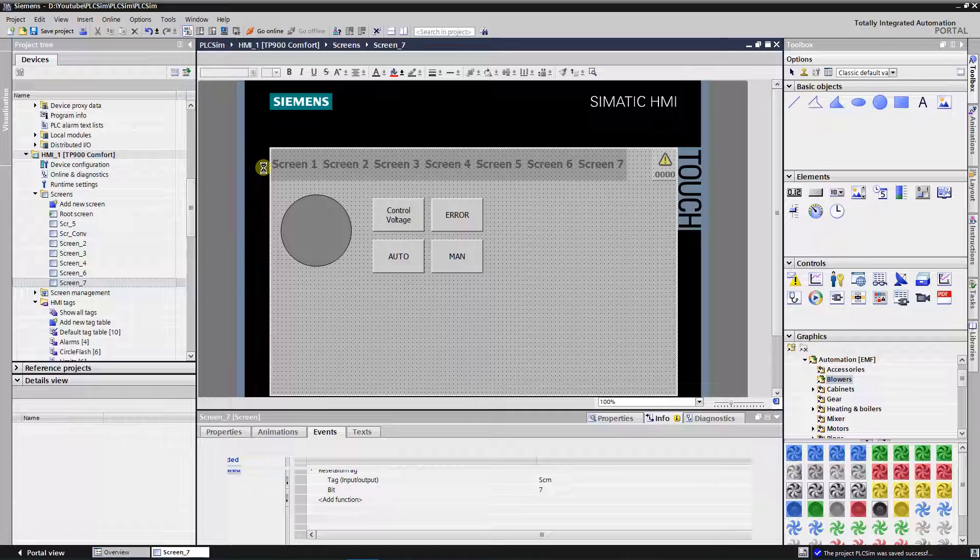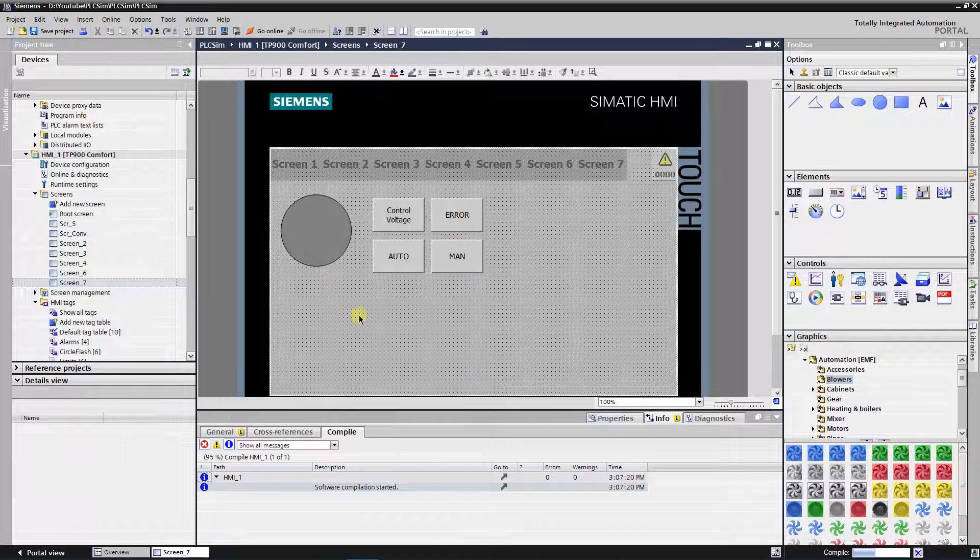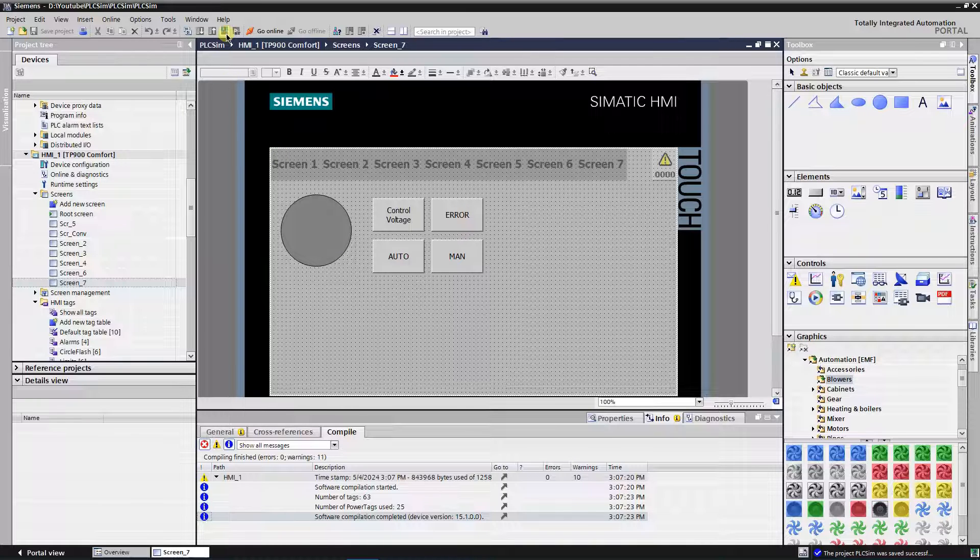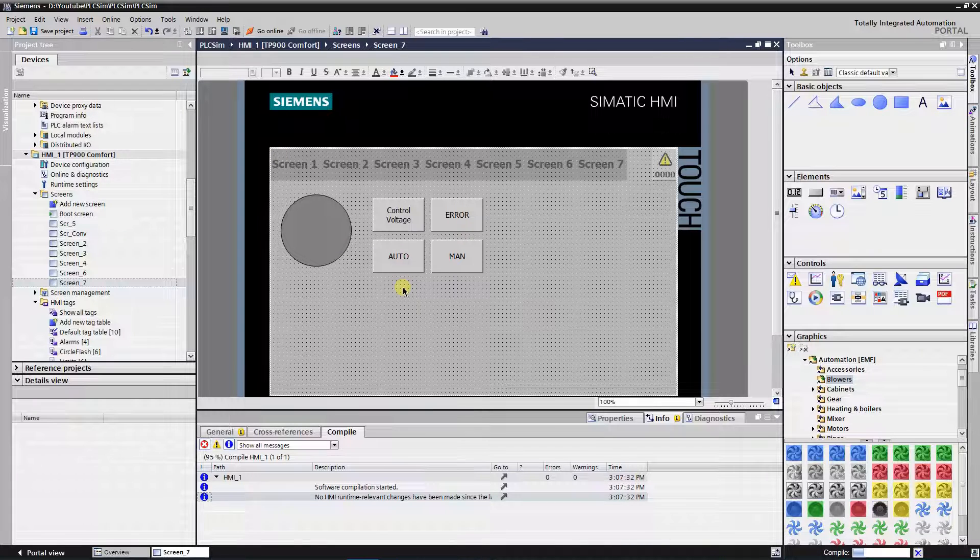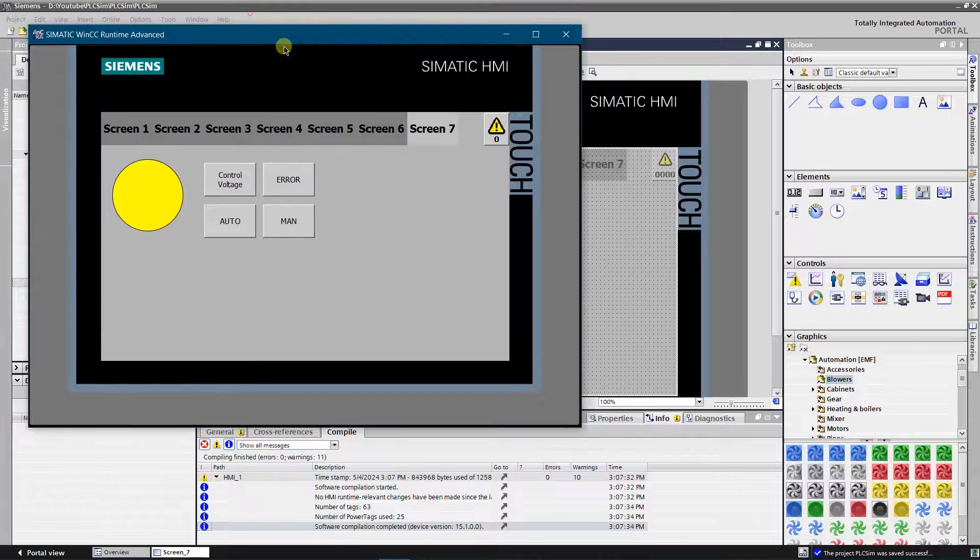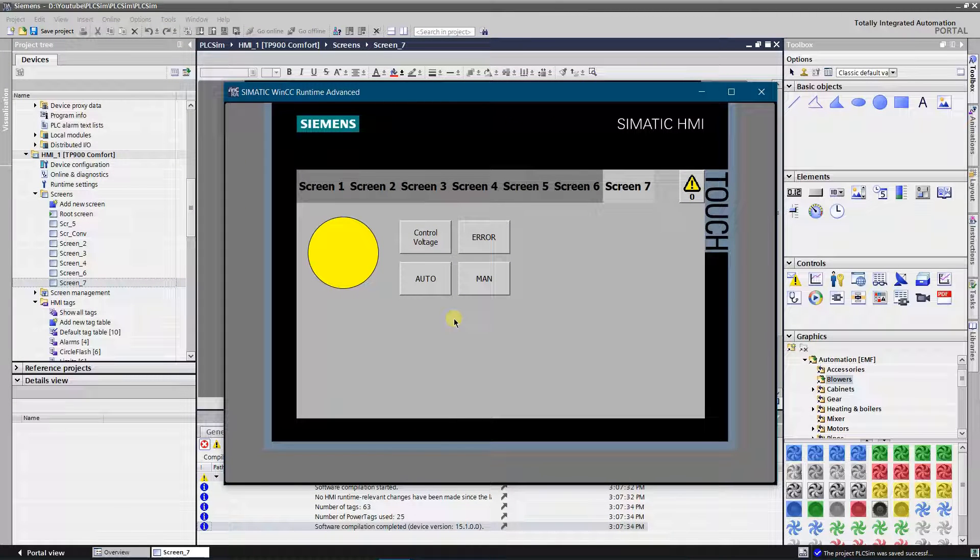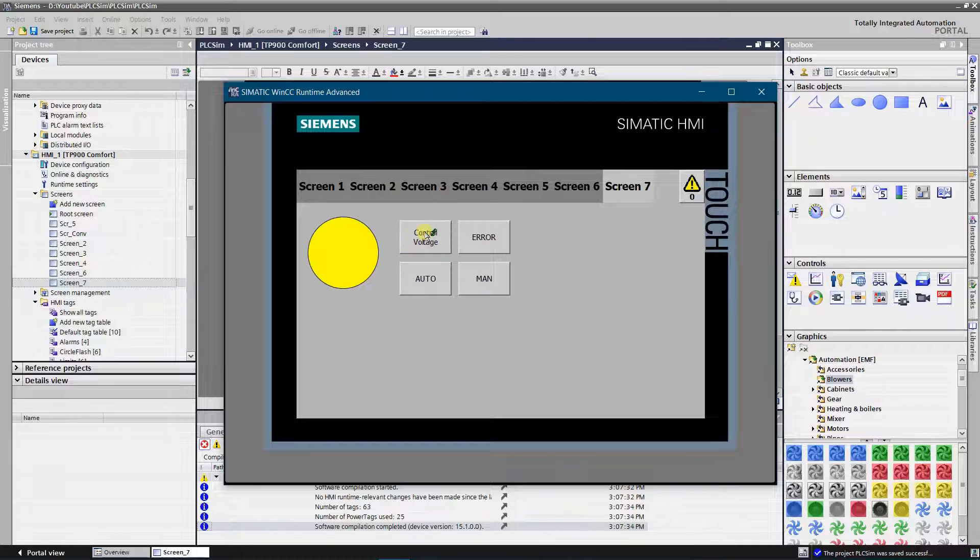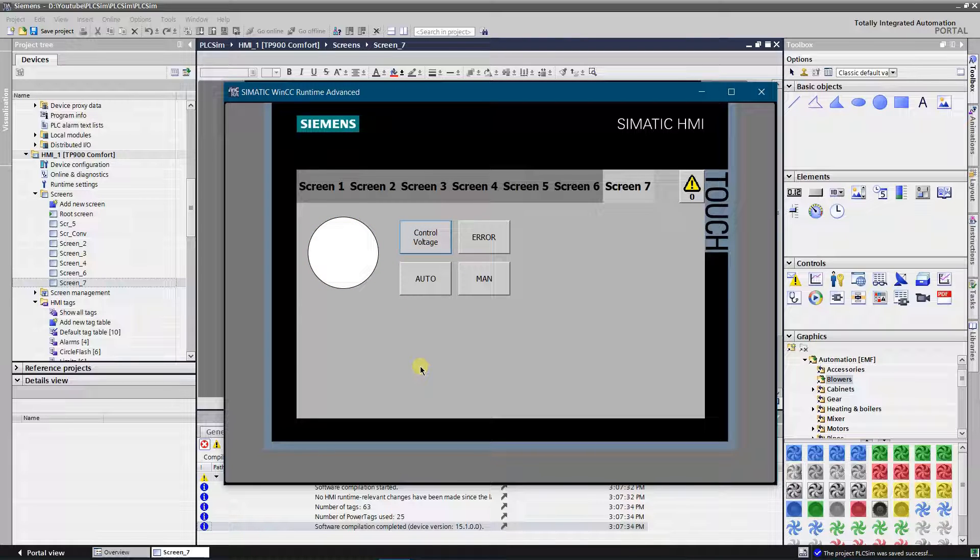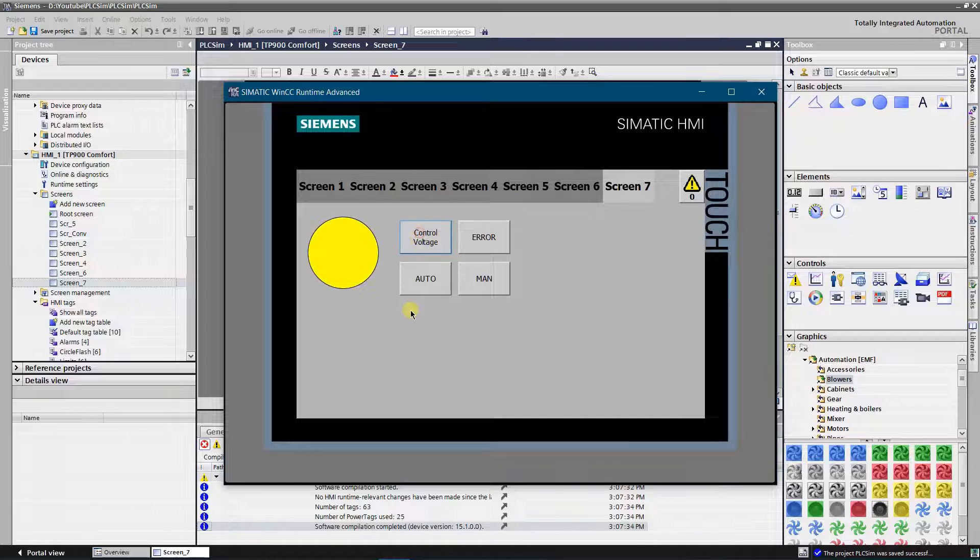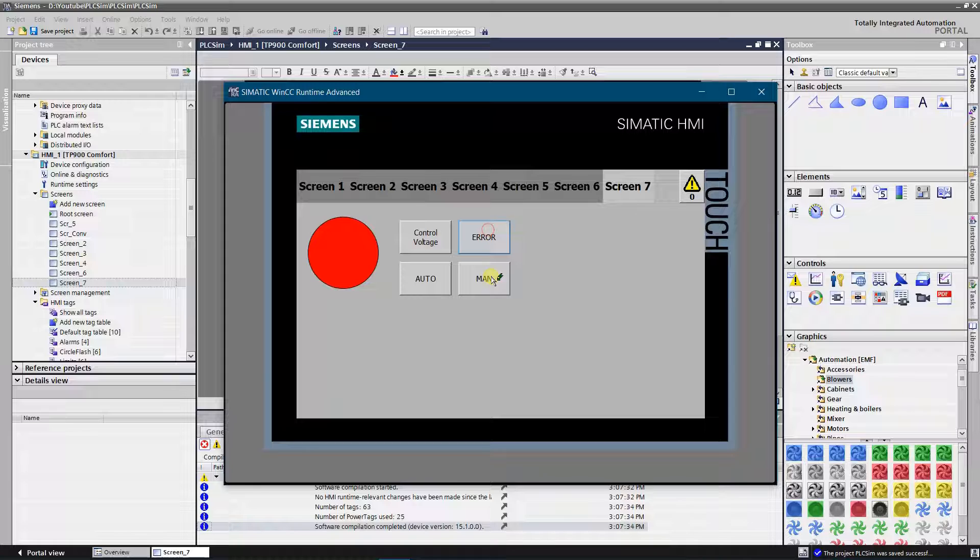Let's test our program. Yellow color of the circle indicates that motor is ready to operate. Let's try to turn off control voltage. Control voltage is off, circle color is white. By putting motor into fault state, circle color becomes red.